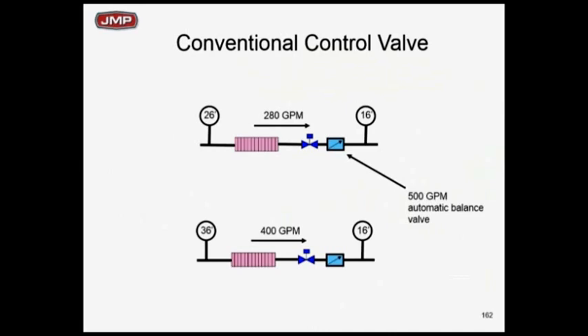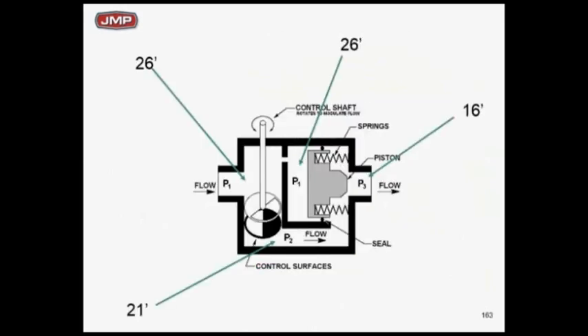So a two-way valve in series with an automatic balancing valve and a flow limiter is not the same thing as a PIC valve. That's a lie. Do not accept that it's the same thing. It is not. Pressure independent control valves keep your delta T up. The flow limiter would help with the total flow. It will never be over 500 GPM. That's all it's going to do for you. So enough said on the PIC valve. You kind of got the concept of how it works.